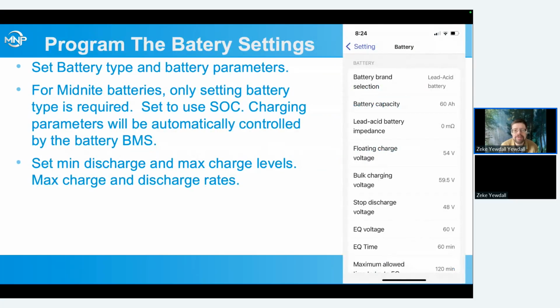First, we want to go in and program the battery settings. We want to set our battery type and our battery parameters. For Midnite batteries, default will be Pylon, which kind of talks to the Midnite batteries, but it's better to set it to Midnite. And then all the defaults for communications protocols will be correct. We want to set it to use state of charge when we're talking to Midnite batteries or any closed loop connection. If we're doing voltage control, we want to set it to voltage instead. We want to set our minimum discharge and maximum charge levels and rates and everything. Again, we'll discuss this more in a different webinar.